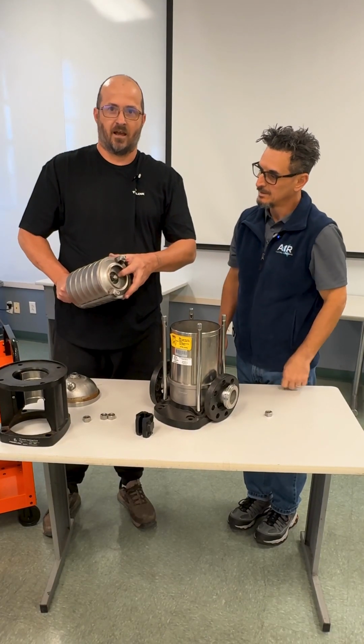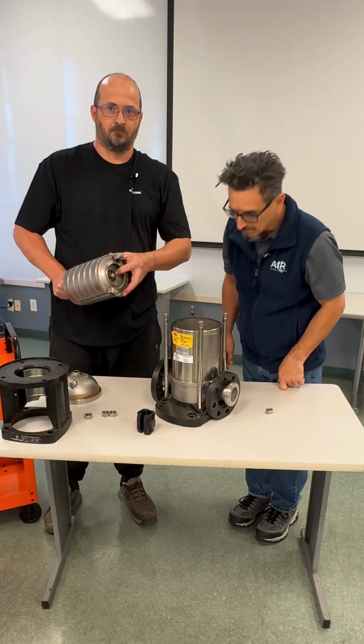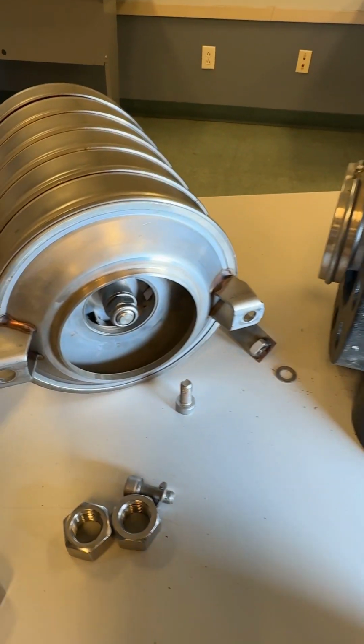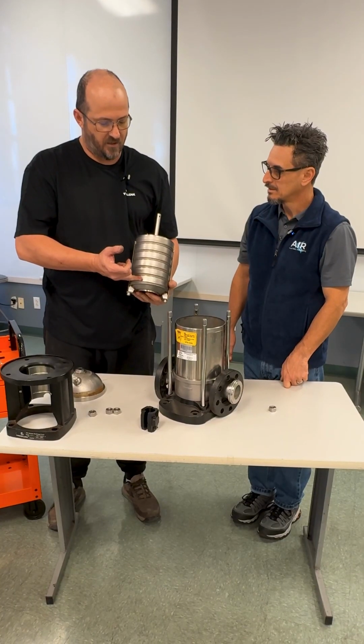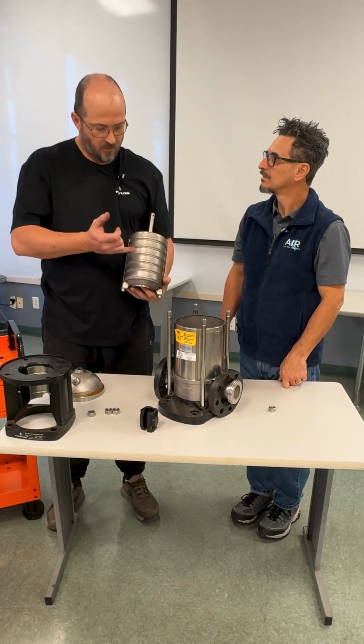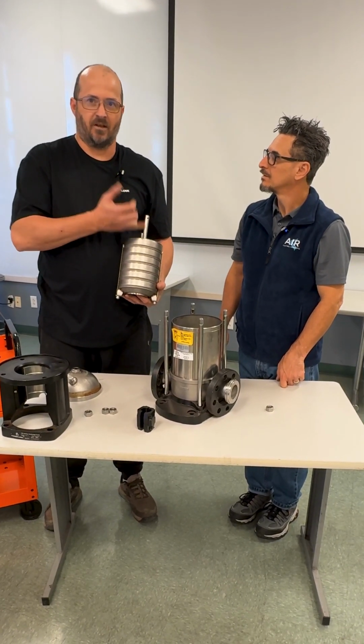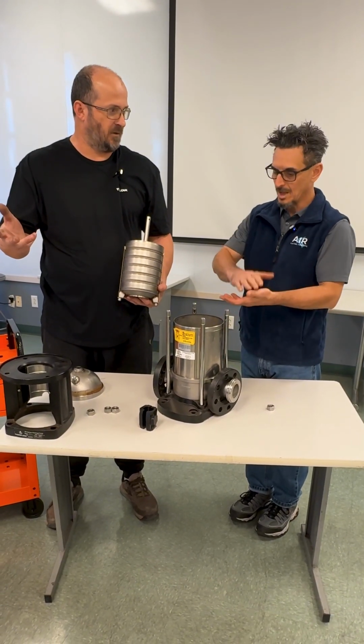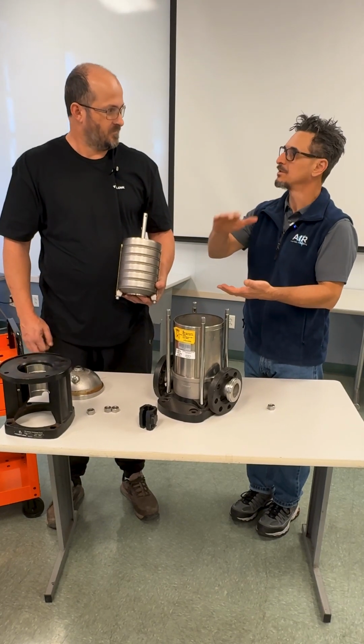This feeds into the impeller stack sitting right on top. As each impeller spins up, it increases the pressure through each stage until it maxes out—stepping it up. That's the purpose of the multi-stage design. Correct.